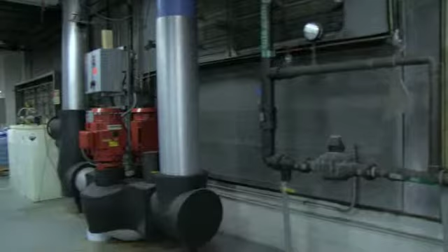Keith just asked a good question. Our chillers in there that I showed you are both 350 tons of refrigeration, a total of 700 tons of centrifugal chiller capability. But out here we added this. When we did Project 1, we didn't have enough capacity to add air conditioning to certain parts of the building with those two chillers. So we added this air-cooled chiller, which is 120 tons, to offset some of the load, but also give us the ability, on light load conditions, to run just a 120-ton chiller as opposed to one or two 350-ton chillers. We have that flexibility. So it's another economical way of utilizing a smaller piece of equipment that is not directly connected to that.